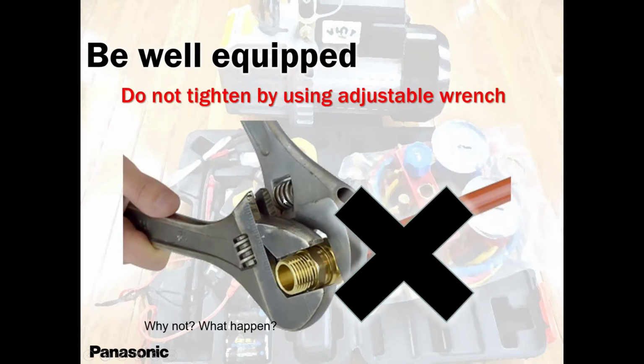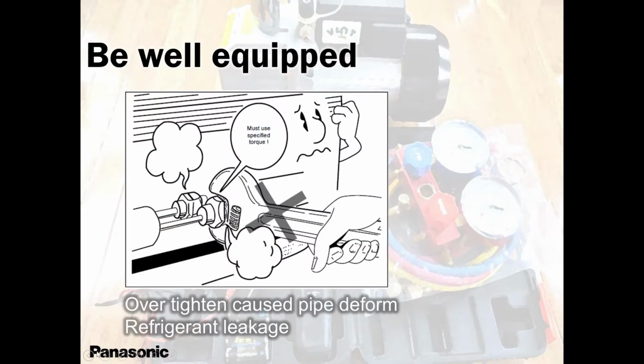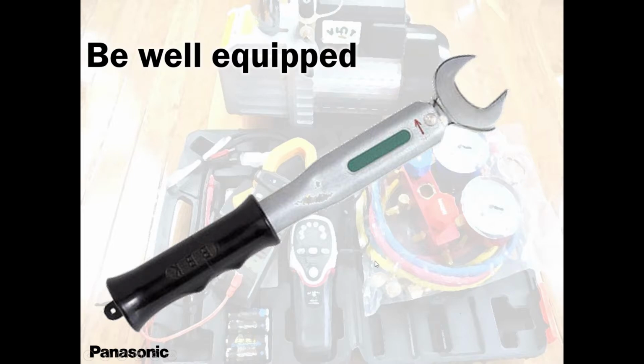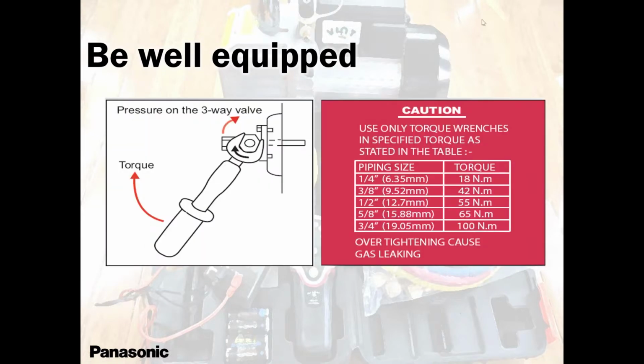Then comes the wrench. I know guys use adjustable wrenches all the time because they know the feeling of their arm, they know they got to the sweet, soft spot. But no, they are wrong. Always use this guy, the torque wrench. I am 30 plus years in this trade, and I still use this tool because I don't trust my feeling of how I tighten, because I know I will crack this down the road. It will leak very minutely. Sometimes a leak can take forever to be seen. Please use torque wrenches. And in all our documents, in all our installation manuals, we have the values here.